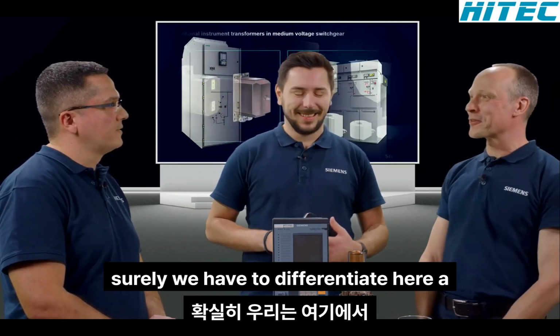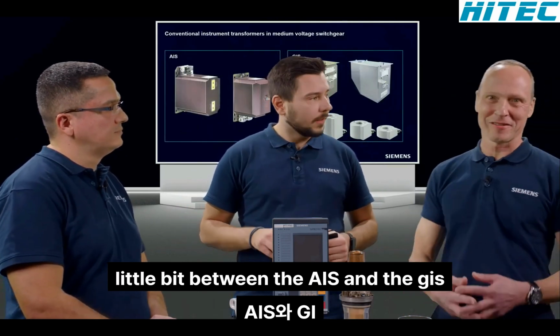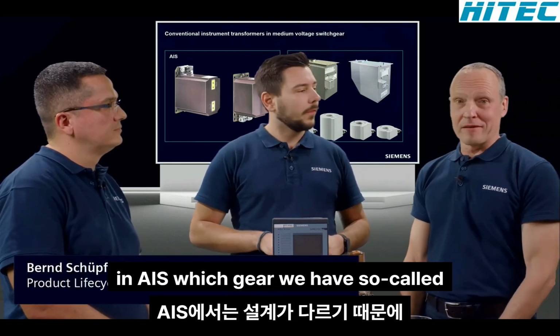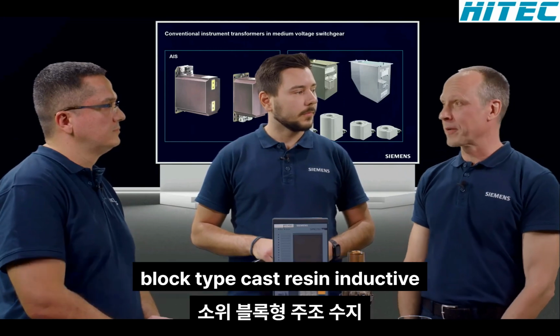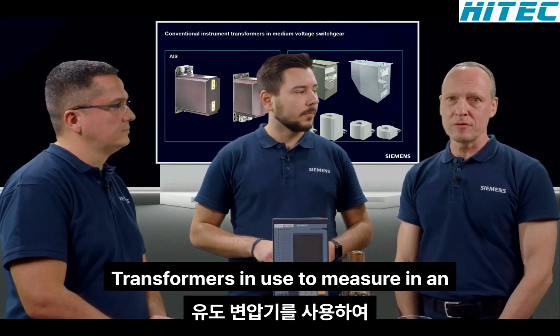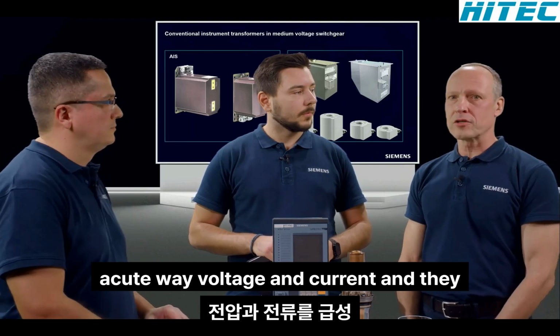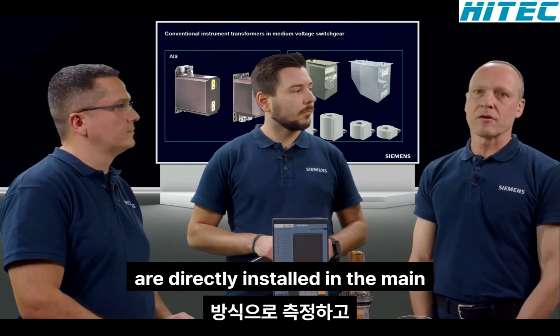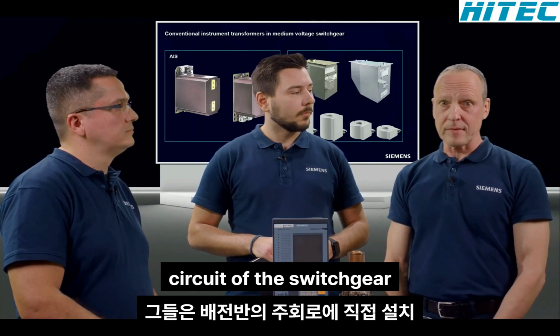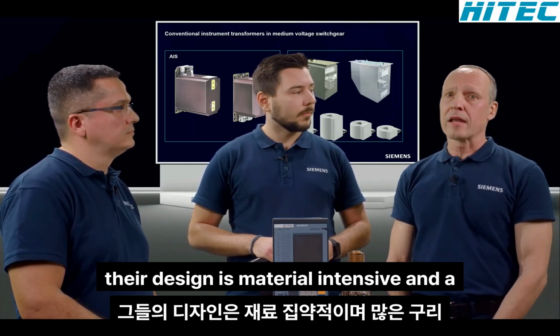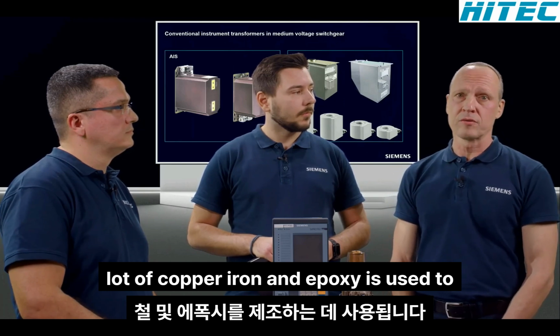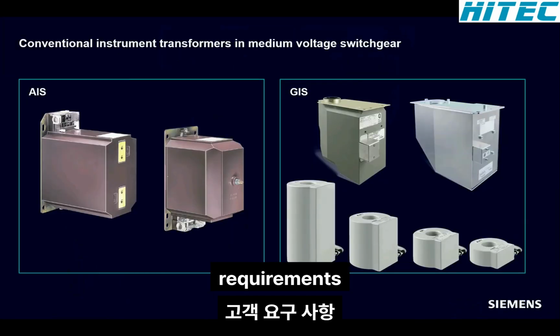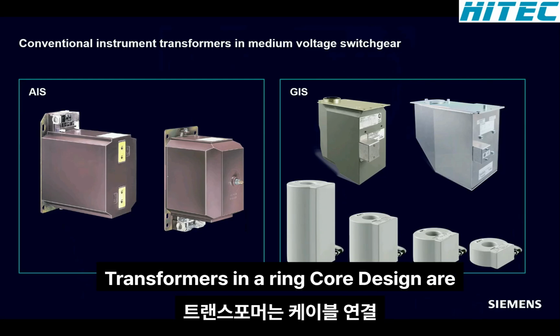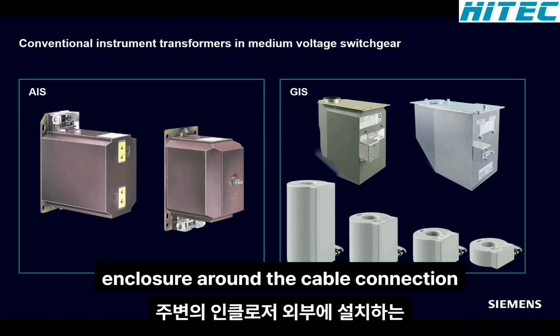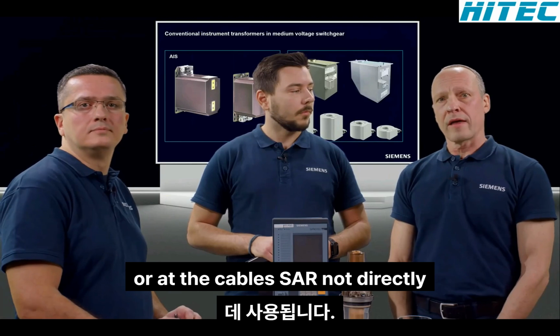Sure, Lars. We have to differentiate here a little bit between the AIS and the GIS switchgear. As the designs are different, in AIS switchgear, we have so-called block-type cast resin inductive transformers in use to measure in an accurate way voltage and current, and they are directly installed in the main circuit of the switchgear. Their design is material intensive, and a lot of copper, iron, and epoxy is used to manufacture them due to customer requirements. In GIS switchgear, inductive current transformers in a ring core design are used to be installed outside the enclosure around the cable connection or at the cables.